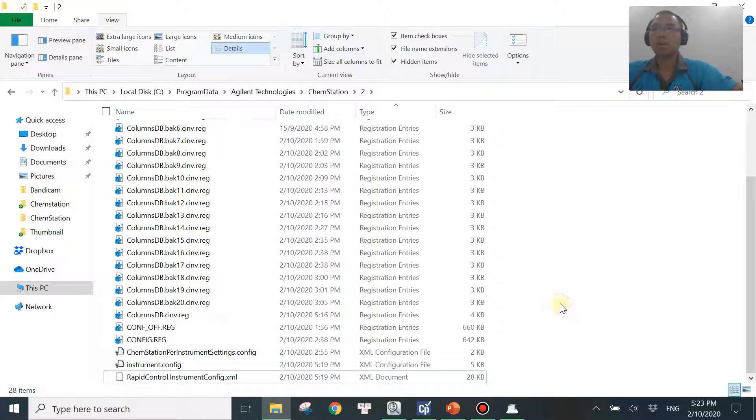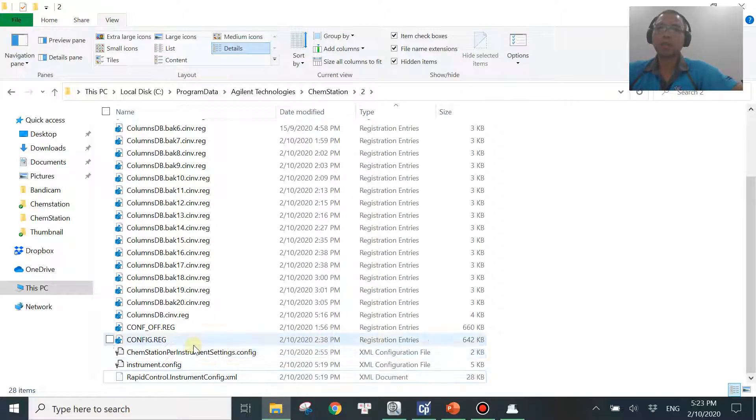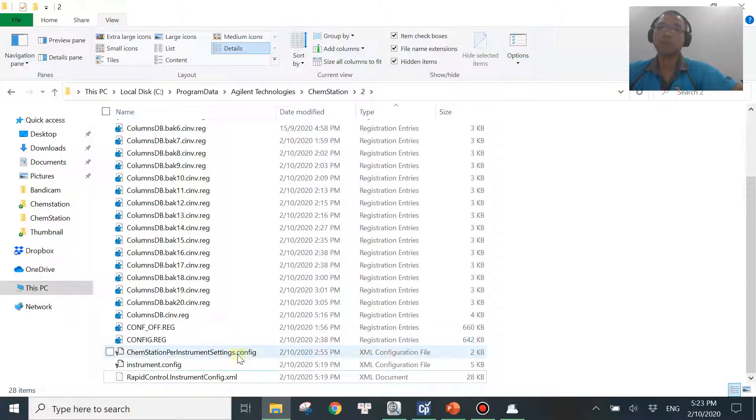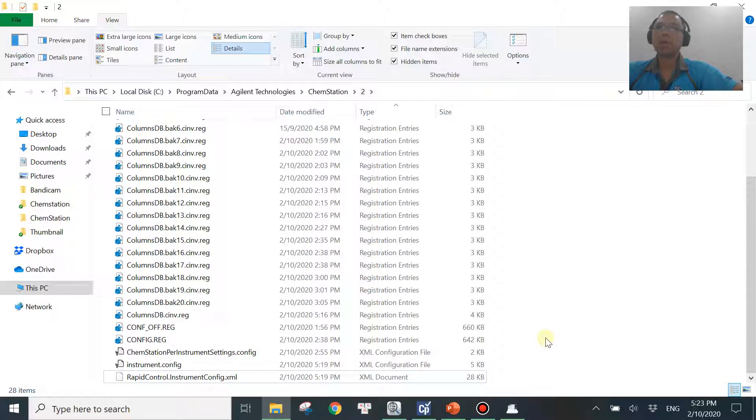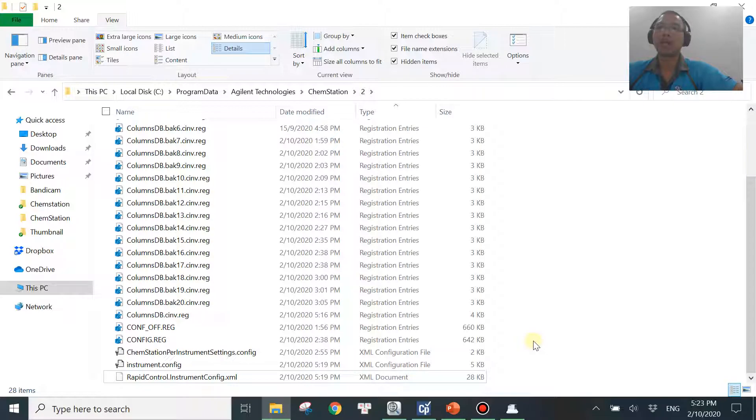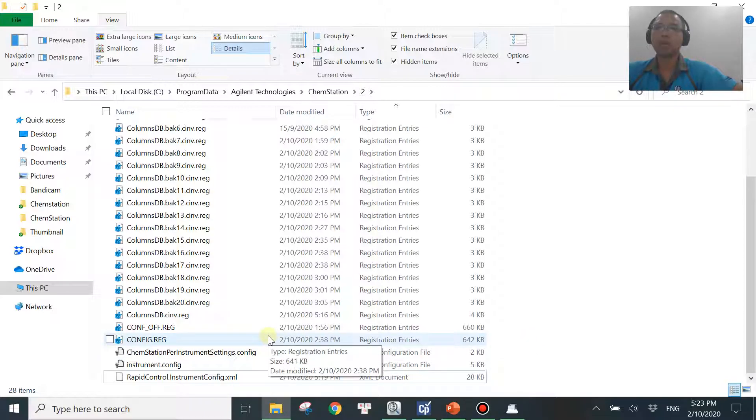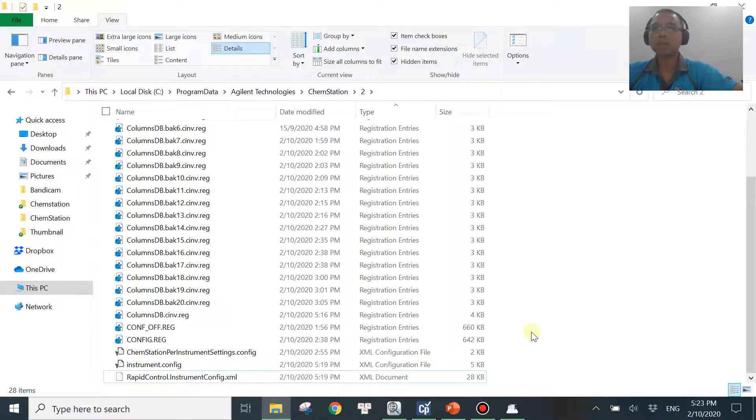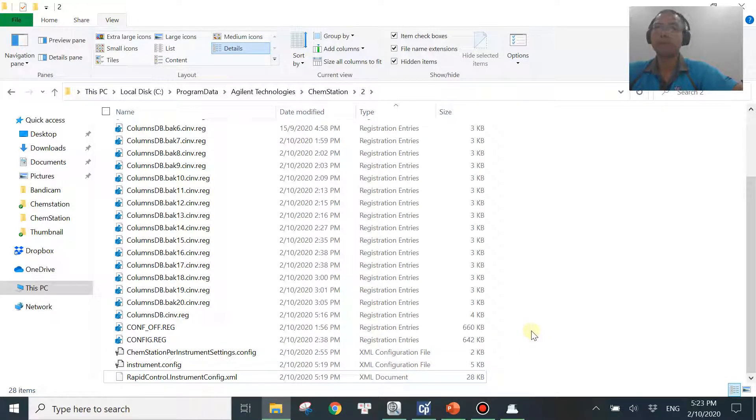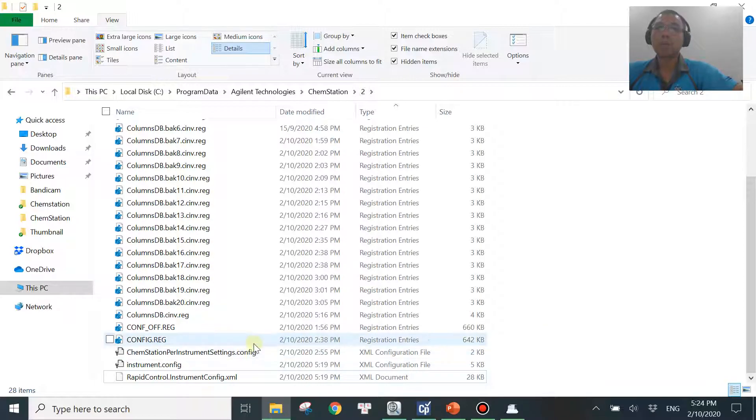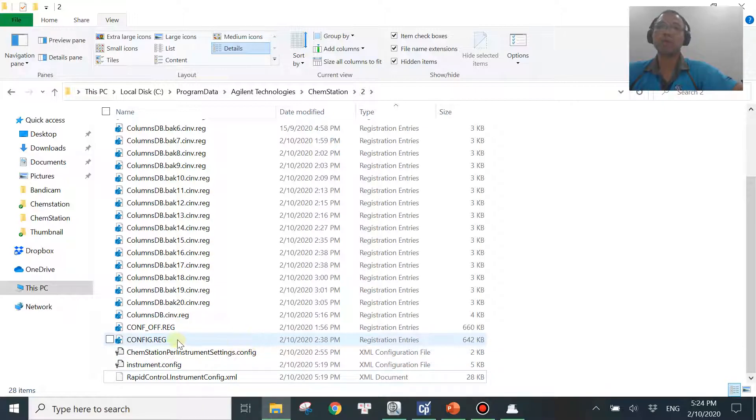So the error message just now is showing 42, and that means one of these four files. Again, we don't know which file it is. It's not important at all to know which file is corrupted. But you will get different numbers depending on which file is corrupted. And the very common numbers that we see will be error 999, triple 9. So one of these files are corrupted. You'll be seeing that very often. But regardless of whether 42, 99, or whatever number it is, the way to fix the problem is the same. So because we don't know which files are corrupted, we basically want to change everything. So that would be a safe way to do.